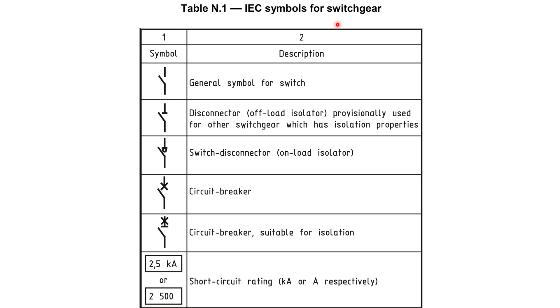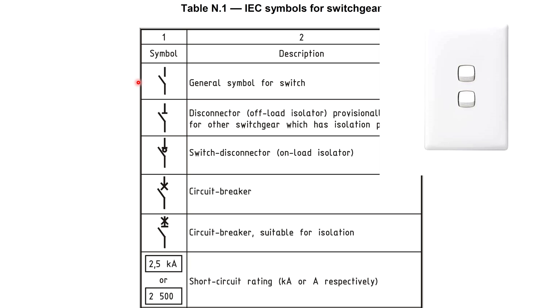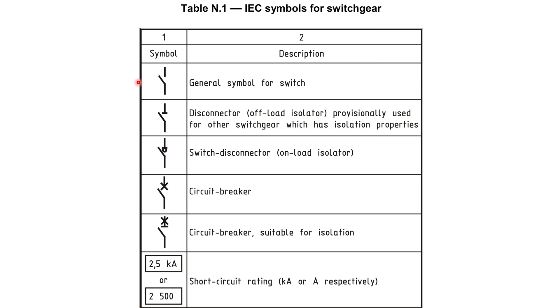Having a look at the IEC symbols for switchgear. Over here, the first one just shows a switch — this is a general symbol for a switch, which would be your light switch. You use your light switch to open and close the lighting circuit under normal conditions. Then we have a disconnector, but note that it says offload. So this means you can disconnect a part of a circuit, but when you do the disconnection, the power must be off and also the load must be discharged. Sometimes the load stores energy — we have to wait for that energy to be dissipated before we open that disconnector.